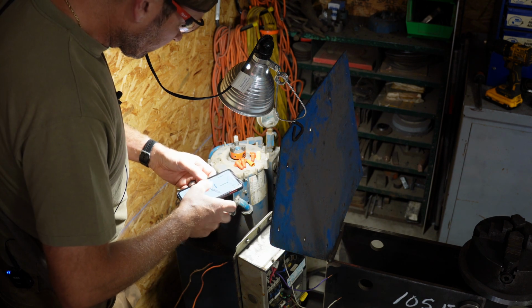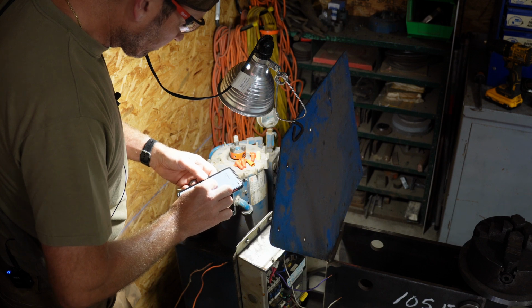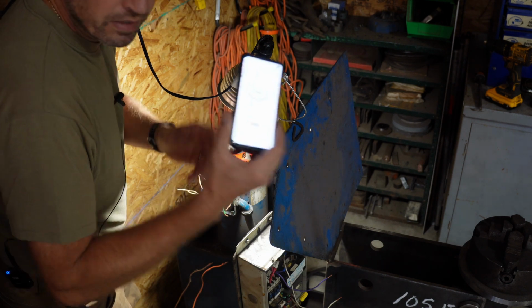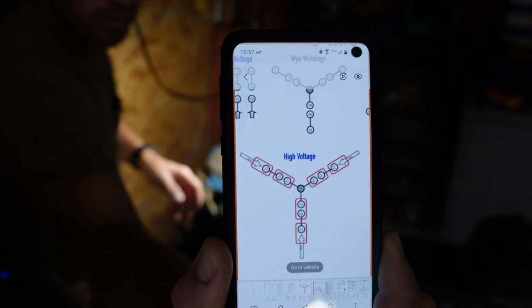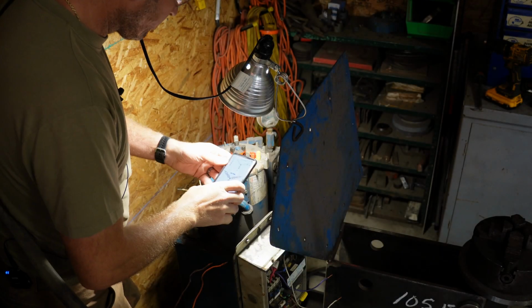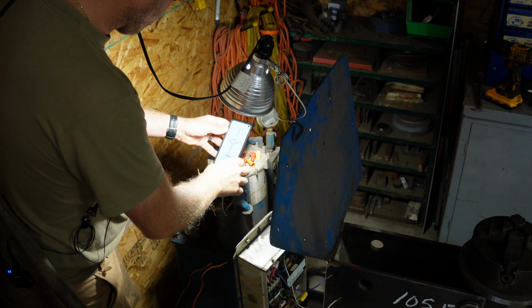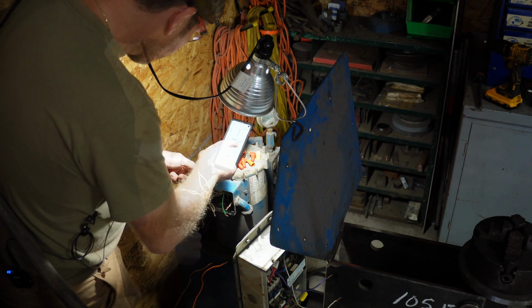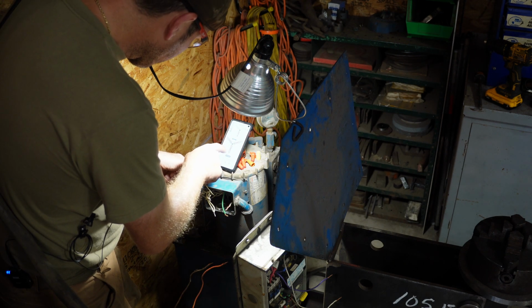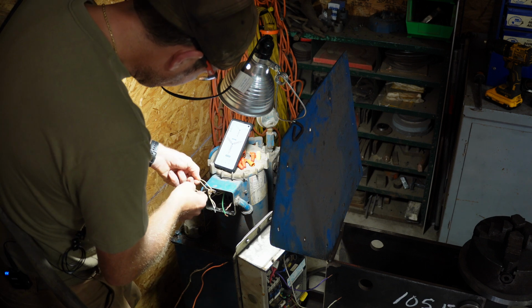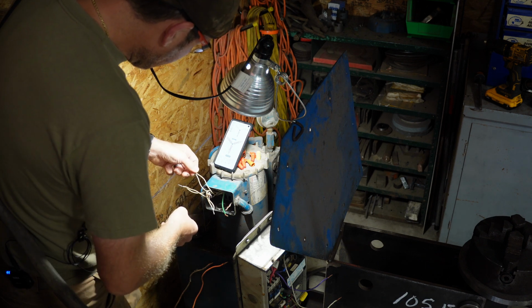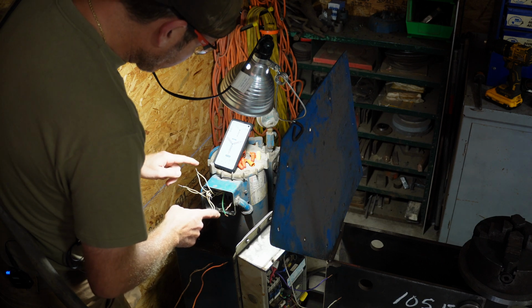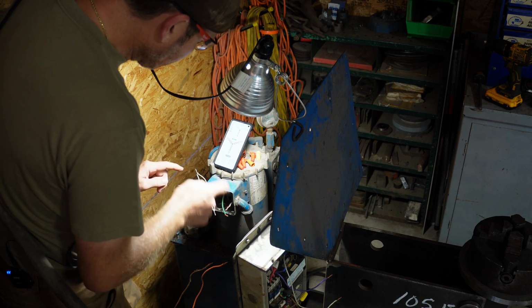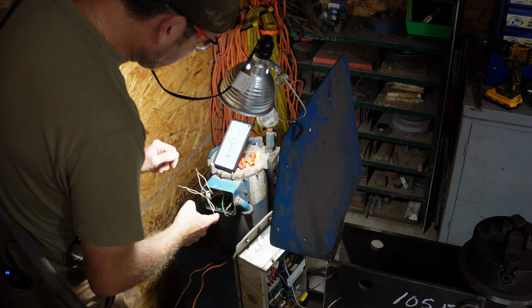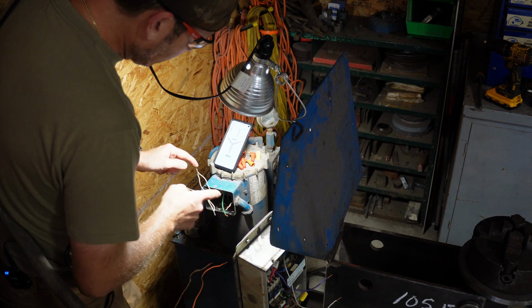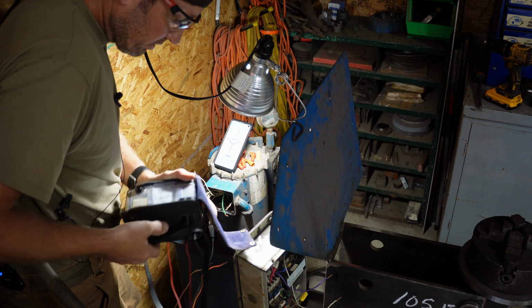This is a Y or star style winding setup, like that. So I'm going to use that to figure out how to check phase to phase: 2 and 5, 1 and 4, 3 and 6. So this one should be 3 and 6. Yep. So now I'm going to check from phase to phase, phase to phase, phase to phase, and then each of these to this one, or this one to each of those. Got to be careful with these things.